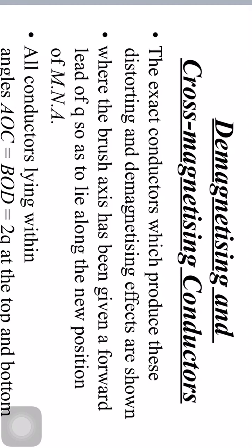Next, this is about the armature reaction. With brushes located along the geometrical neutral axis, there is no demagnetizing component of armature reaction. There is only a distorting or cross magnetizing effect of armature reaction. With the brushes shifted from the GNA, armature reaction will have both demagnetizing and distorting effects. Their relative magnitudes depend on the amount of shift. This shift is directly proportional to the armature current.